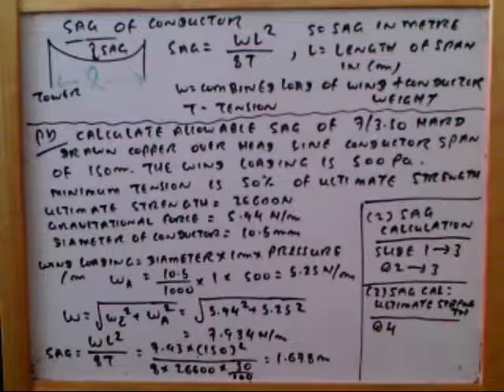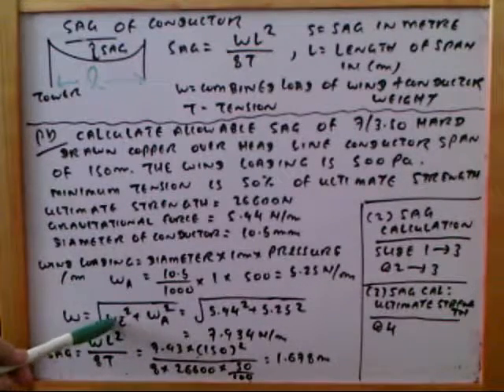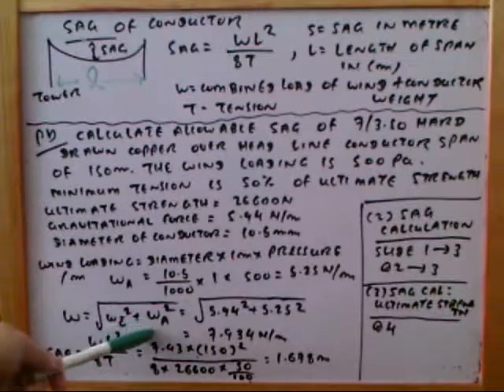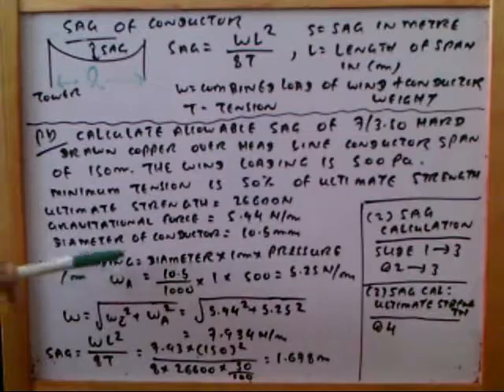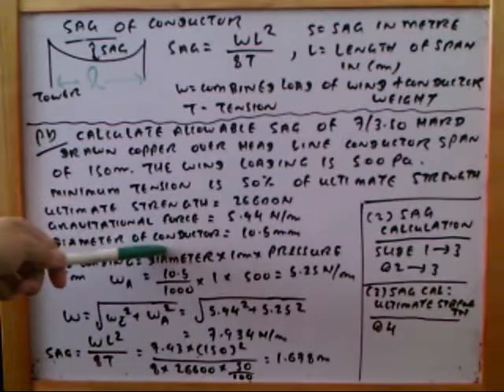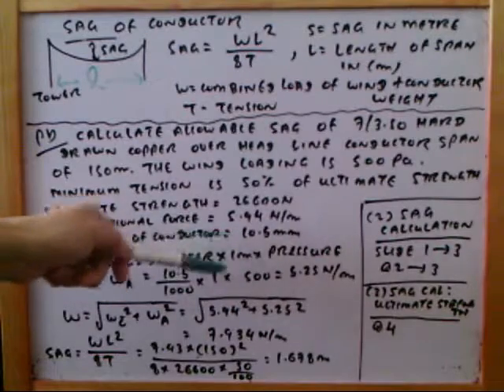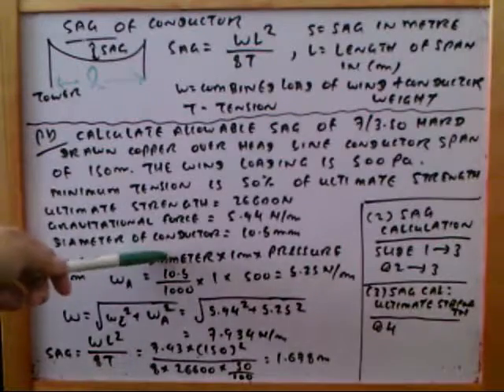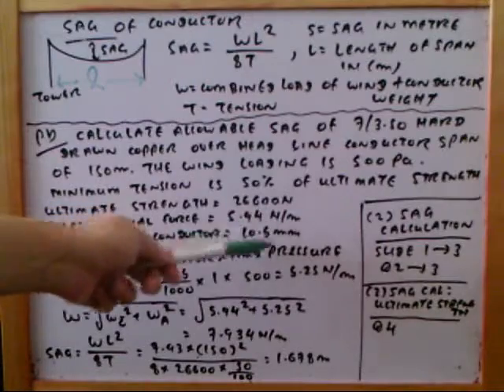The total weight w is calculated as: w = √(wc² + wa²), where wc is the gravitational force and wa is the wind force. The wind loading wa is calculated as: diameter × 1 meter length × wind pressure. We consider the wind loading per 1 meter length.